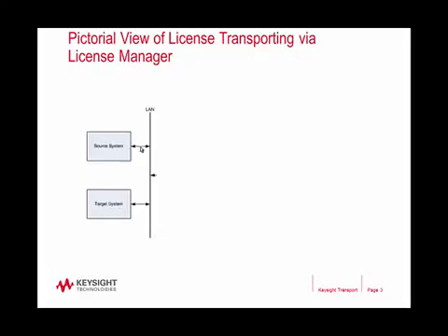If you have LAN access to both of those, you can use a third computer and run a tool downloadable from our website called Keysight License Manager. That is PC software that connects to both the source and the target in such a way that it will handle the transporting for you.